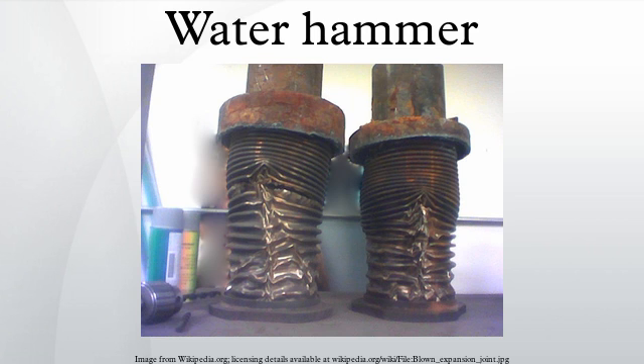On the other hand, when an upstream valve in a pipe closes, water downstream of the valve attempts to continue flowing, creating a vacuum that may cause the pipe to collapse or implode. This problem can be particularly acute if the pipe is on a downhill slope. To prevent this, air and vacuum relief valves, or air vents, are installed just downstream of the valve to allow air to enter the line for preventing this vacuum from occurring.